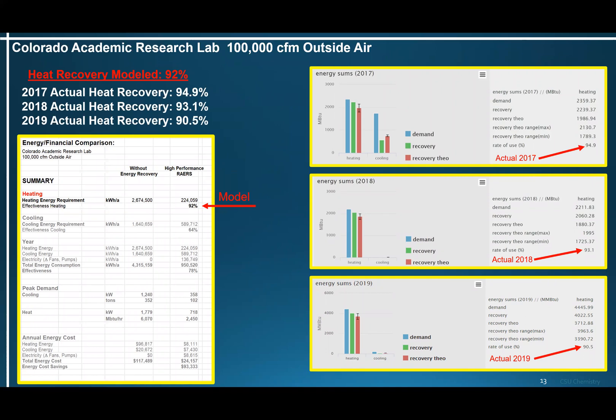Let's look at some model results versus actual post-occupancy results. This is an academic research lab in Colorado with 100,000 CFM of outside air. The model calculated 92% annual heating effectiveness, meaning 92% of the annual heating requirement comes from recovered energy. Actual post-occupancy results: 2017 — 94.9%, 2018 — 93.1%, and 2019 — 90.5%. So pretty close to the model.